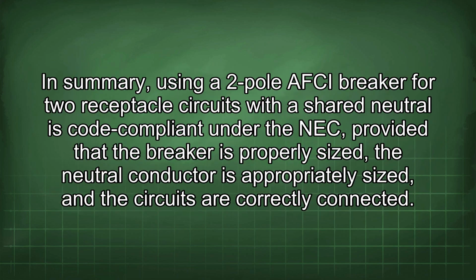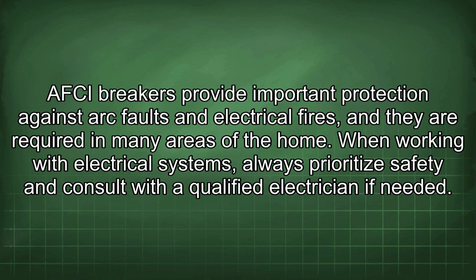In summary, using a two-pole AFCI breaker for two receptacle circuits with a shared neutral is code compliant under the NEC, provided that the breaker is properly sized, the neutral conductor is appropriately sized, and the circuits are correctly connected. AFCI breakers provide important protection against arc faults and electrical fires, and they are required in many areas of the home. When working with electrical systems, always prioritize safety and consult with a qualified electrician if needed.